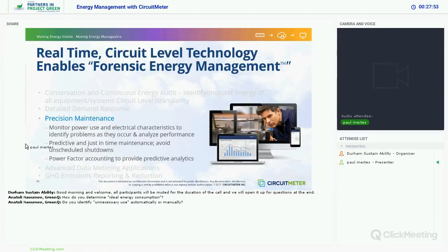I talked a little bit about precision maintenance, but in addition to understanding when an incident occurs through increases in current draw, or when deterioration starts, which begins a repair-or-replace decision, we can add value by understanding exactly when maintenance is needed, so we don't over maintain. Quite often we have scheduled maintenance regimes with a factor of safety because the cost of breakdown or shutdowns is too high, and that leads to over maintenance. With this advanced electrical information, we can generate a lot of value by moving to more of a precision type of mode.